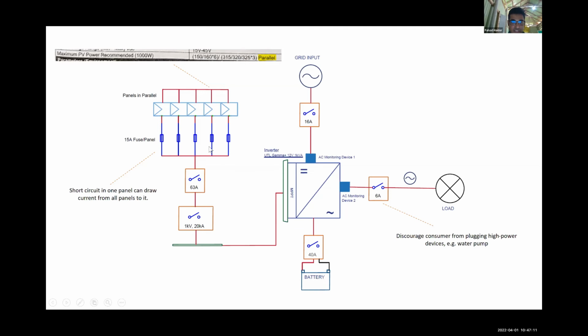Why? This isn't common practice because it takes a lot of resources and effort, frankly. However this should be done because if there's a short on one of the panels, the electricity will follow the path of least resistance, so it won't go through here, it'll go through there, and all the current will go through there. So to stop that, this breaks - that's why we put a fuse. We actually use an MCB after each panel, and then this is the total, to ensure that the total current from all of them combined doesn't exceed the limit.